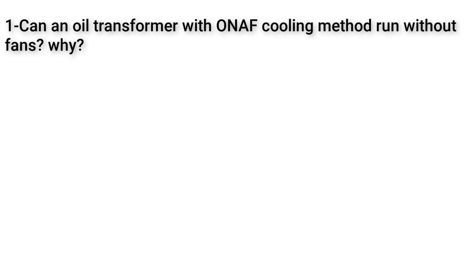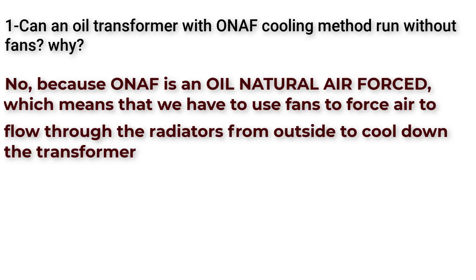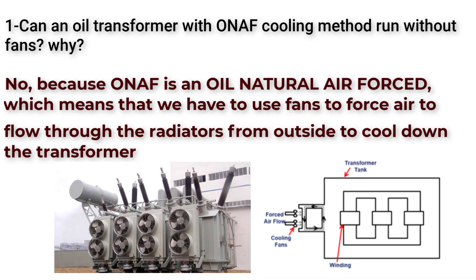The first question here is can a transformer with ONAF cooling method run without fans and why? Well, the answer here is no because ONAF stands for Oil Natural Air Forced. Here we use fans to force the air to flow through the radiators from outside to cool the transformer.